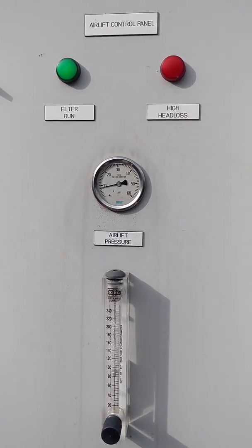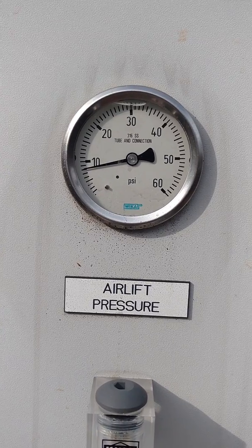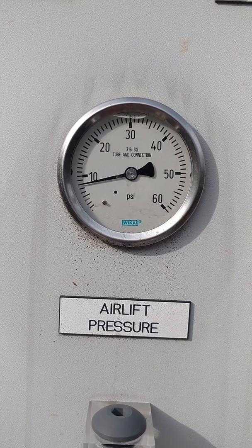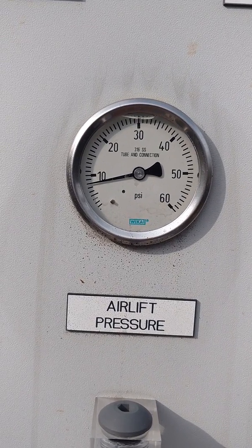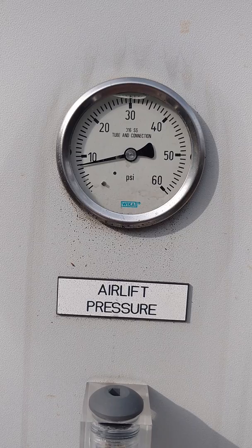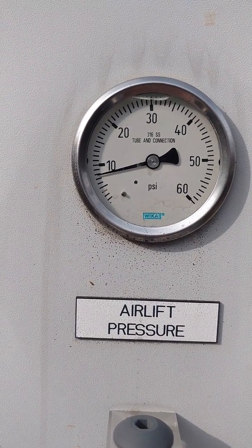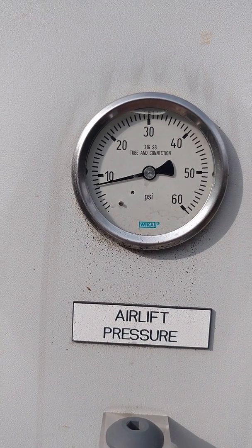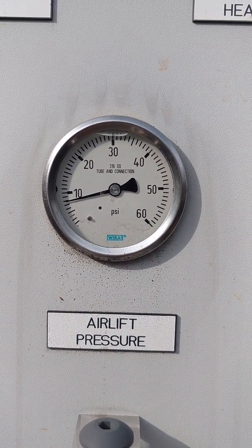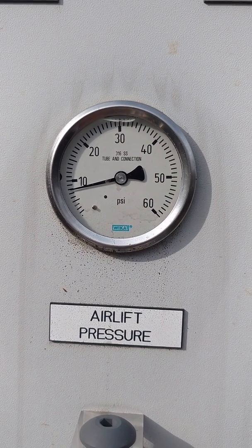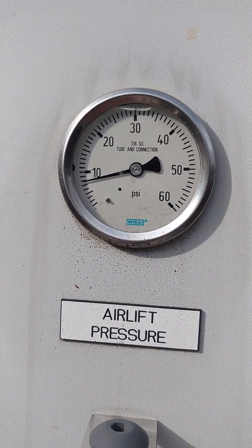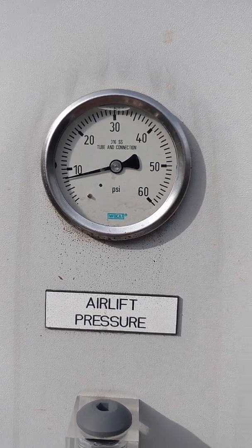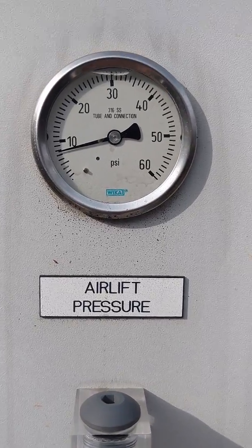Right now, here are the gauges. The airlift pressure, you want it between 9 to 11, 9 to 12, in that range. Right now it's reading 8. Less is better. When you get up around the 15 range, that means your filter is not working consistently. Your airlift potentially is stopped up. That is the center pipe going down into the filter that's pulling the sand up.